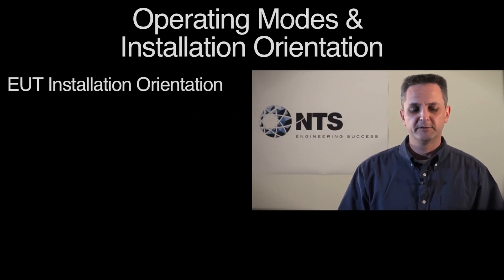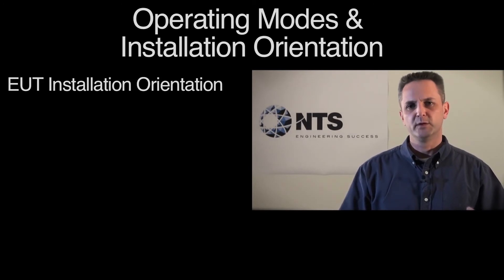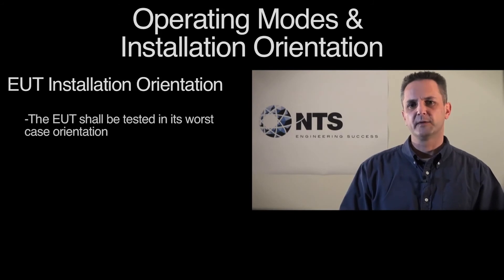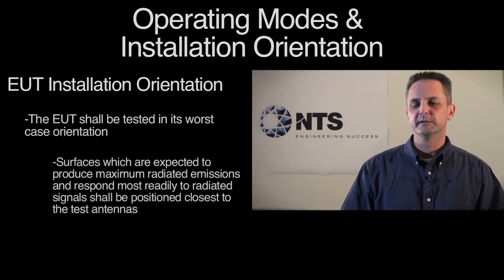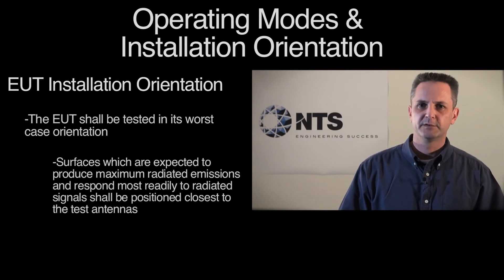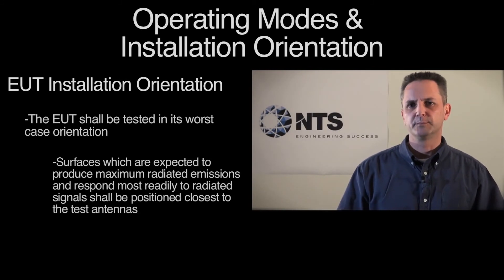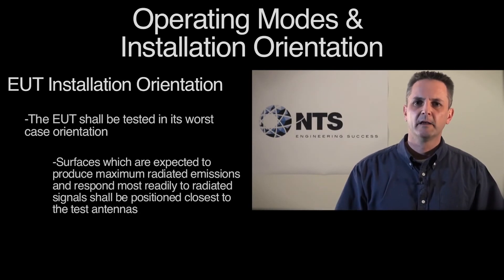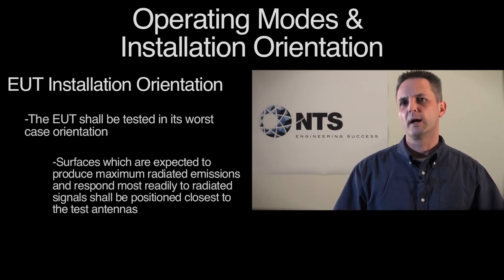Next is EUT installation and orientation. MIL-Standard 461F doesn't specify exactly how the equipment should be oriented, but it does specify that the orientation which could produce the greatest emissions, or be most vulnerable to a radiated or conducted field, shall be positioned closest to the transmit antenna — mainly important for radiated susceptibility and radiated emissions testing. Earlier revisions of the standard allowed near-field probing, using a spectrum analyzer and a near-field loop waved slowly over the equipment to determine peak amplitudes, but due to improper use, that requirement has been dropped in MIL-Standard 461F.